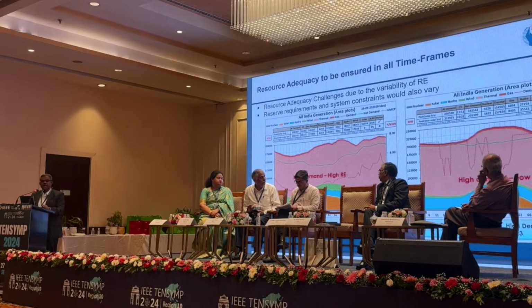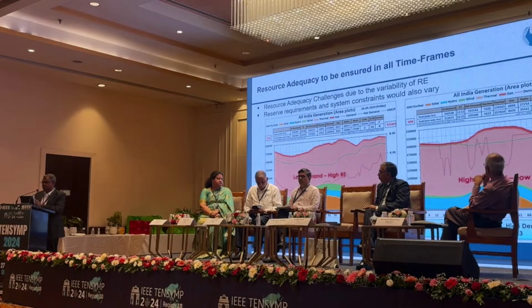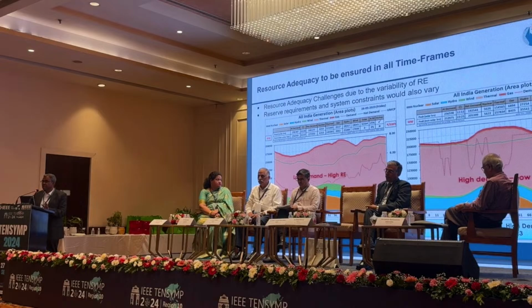In contrast, on the high demand and low RE day on the right, wind is hardly present and only solar is there, and the net load is almost flat throughout the day. With these uncertainties and variability in RE, resource adequacy becomes very important, so you must plan for it. In fact, on this high RE penetration day, the instantaneous penetration was 31%, recorded on 26th of May 2023 - 31% of the country's demand was being met through RE. This is a huge number, and if it disappears, other resources must be called in.